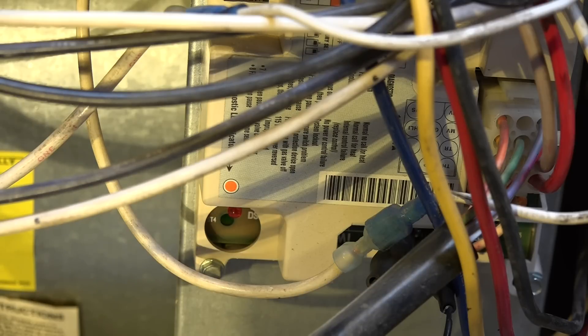What it's trying to do here is it's saying well maybe I had a problem, a bird was sitting on the vent. I doubt that's going to be the problem but there was something in the vent. Let's try again and see if whatever was in the vent is gone. So that's one of the things about these types of controls is they don't just shut off and stay off. They'll actually keep trying to get the furnace to operate.